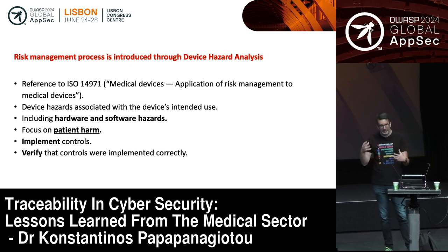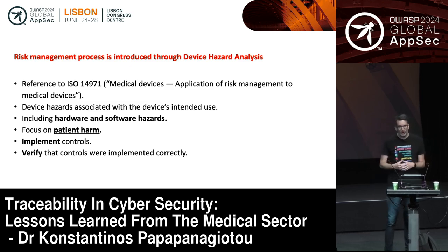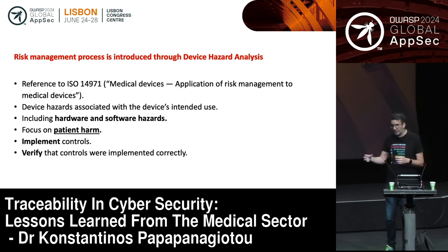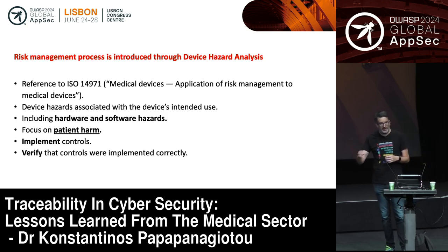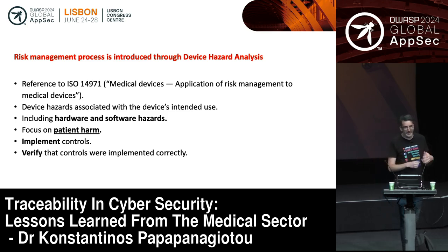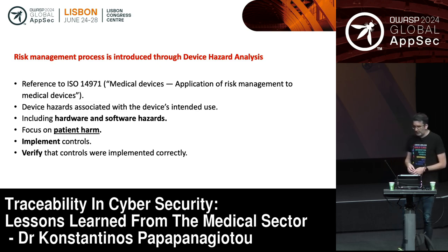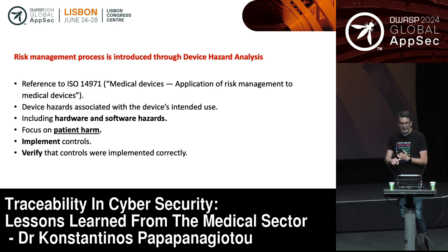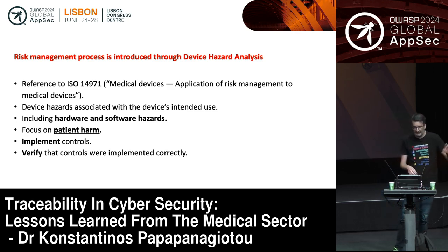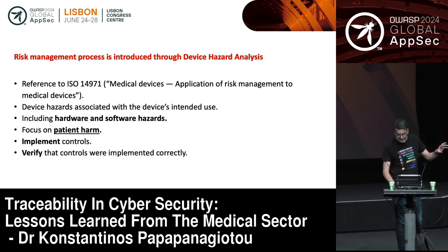So it started talking about vulnerabilities or things that may potentially cause patient harm. FDA cares about patient harm, cares about what's going to happen to the patient if something is not working well on the device. So you need to understand what the risks are, implement controls, and verify that these controls are implemented correctly. That's what FDA said in 2005, which is pretty advanced.